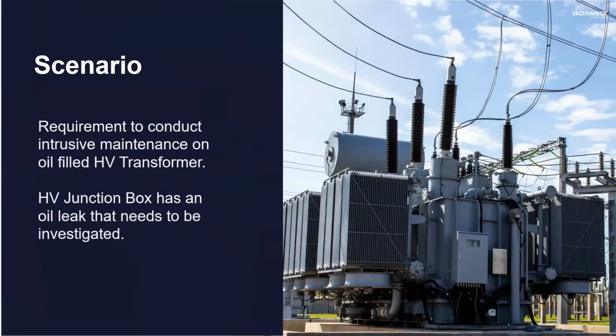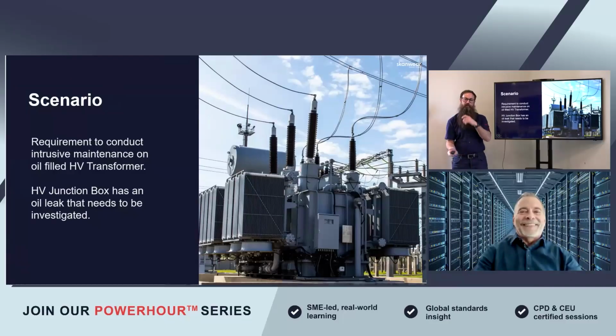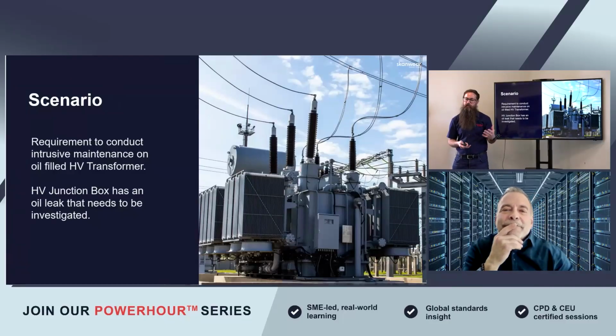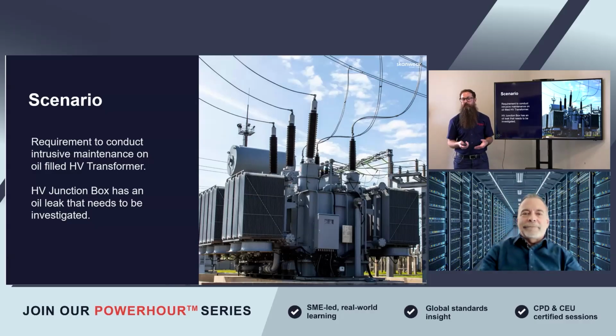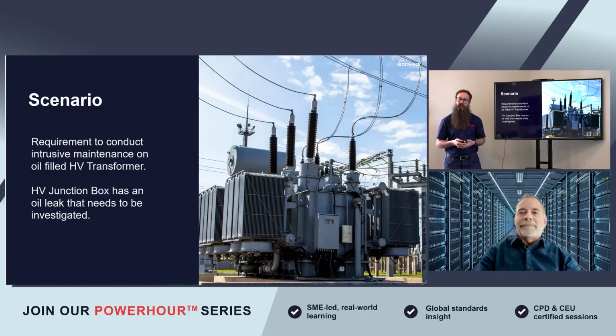Yep. Thanks, Wayne. Back to me, I guess. So we're talking about switching now. We've done boundaries and looked at some of the things that we'll do in the work planning. Now we're going to look at a process to follow for switching. Again, if you're doing things differently, let us know because it'll be good. We're going to look at an example: a simple isolation on a single feed transformer to conduct some intrusive maintenance on it. It's an oil-filled or fluid-filled transformer, and we've got an oil leak on the HV or MV junction box that we need to investigate.